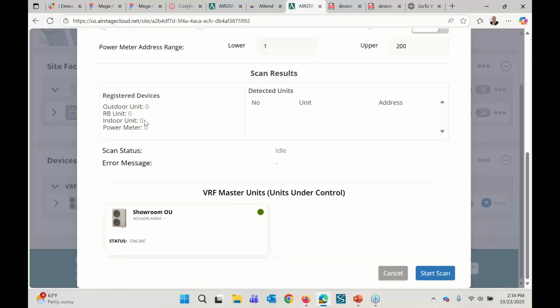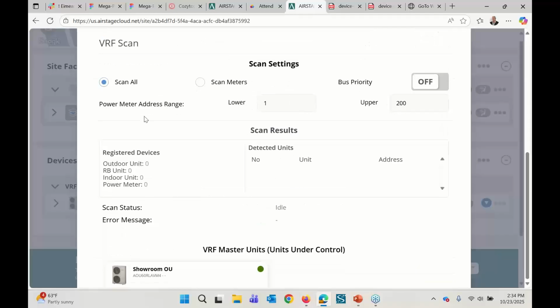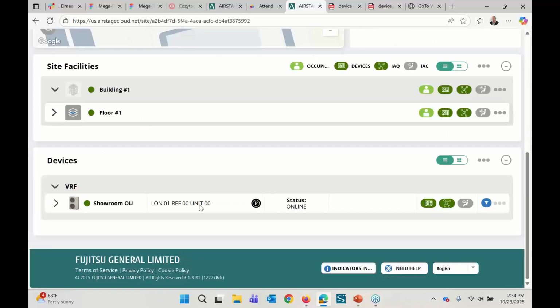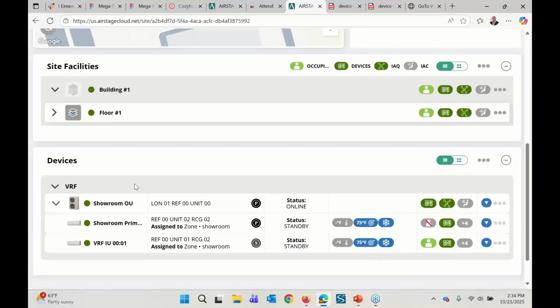Once that VRF scan runs, it will tell you how many outdoor units, branch box units, and indoor units it found. You want this data to match your design sim file. If everything matches and you can visually see those units, you know everything has been wired and addressed correctly.